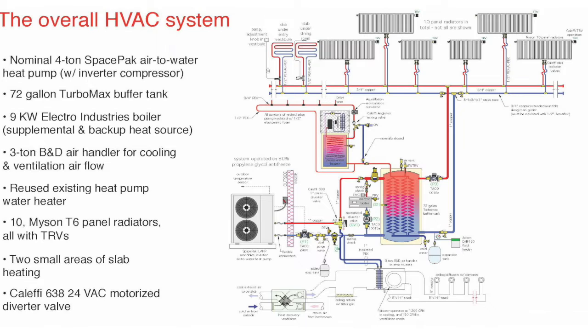The buffer tank is a TurboMax tank, like the tank that's over here now, and it does two things for us. It provides buffering, because we have a lot of independently controlled panel radiators up here. All these panel radiators have thermostatic radiator valves. So there's literally 10 different zones, if you will, 10 different points where you can adjust this, plus the 2 areas of radiant floor heating. You can see those tagged on over here on the left side.